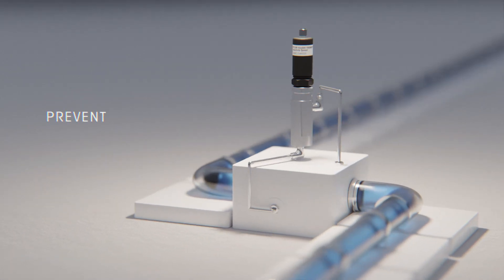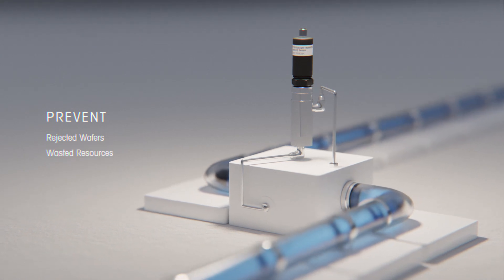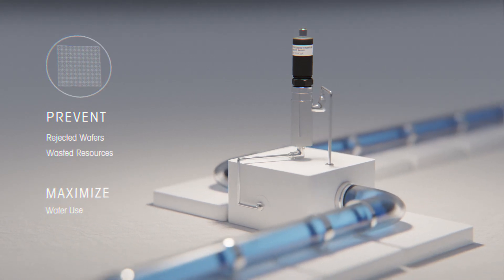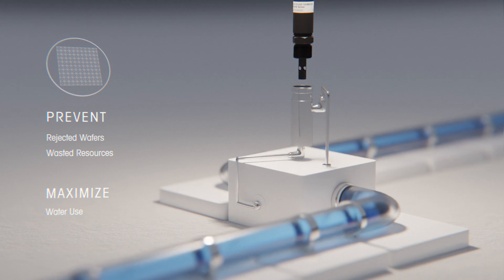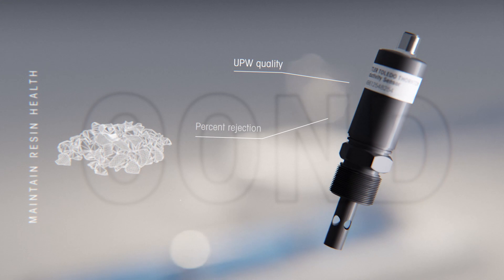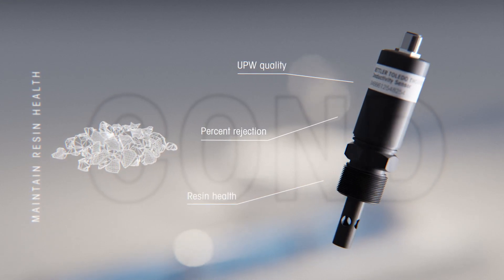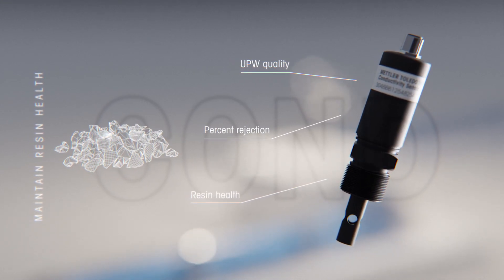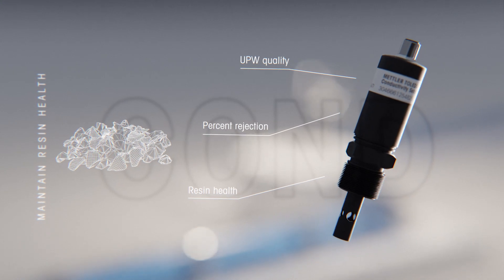Real-time analysis of analytical measurements is central to preventing rejected wafers, wasted resources, and maximizing water use. In UPW generation, use conductivity sensors to monitor ultra-pure water quality, percentage of rejection, and resin health to prevent waste and unnecessary resin replacement or maintenance.